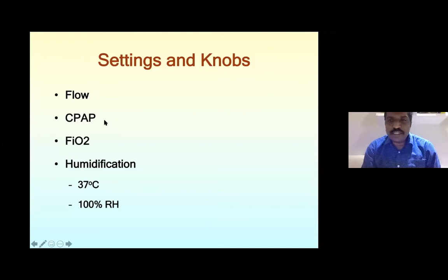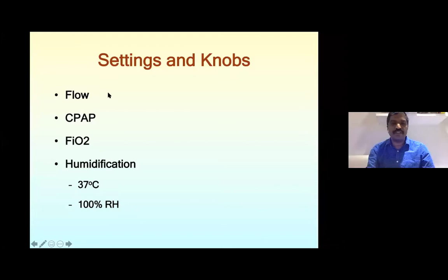So now comes to the settings. Now we have already started. We have started with a flow of 5 liters with a CPAP pressure of 5 centimeters, FiO2 30%. We said humidification, there is no range. 37 degrees Celsius, 100% relative humidity. So that is fixed because you have humidifiers which come fixed. They are servo humidifiers. So you have the option of only 3. In this, we are fixing the flow also at 5 liters. So leftover is only CPAP and FiO2.